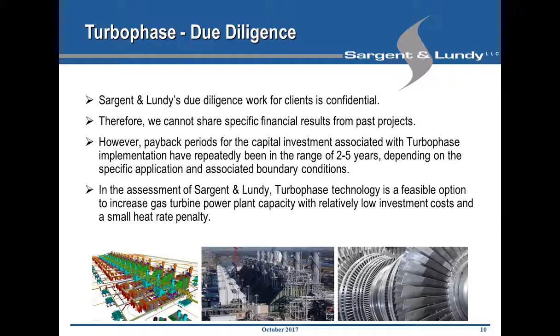But very clearly, all the projects we have looked at, and there are numerous of those projects, have shown payback periods that are quite short. Typically, I would say 2 to 5 years, which is quite good given the opportunities and possibilities associated with the technology and the very limited risks and disadvantages associated with the technology. And therefore, we clearly see the technology as a feasible option to increase the gas turbine power plant capacity at very low risks, small heat rate penalty, and relatively low investment costs.